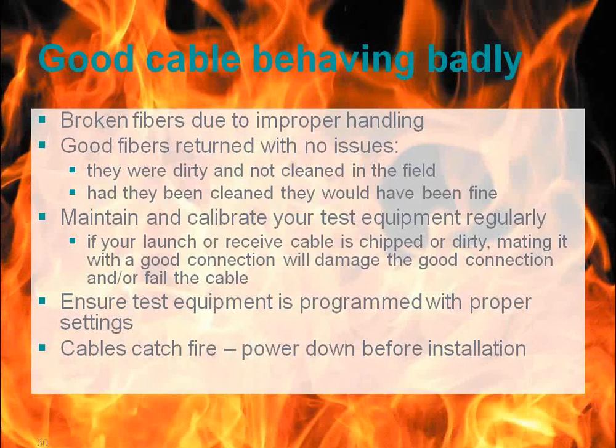Good cables behaving badly. We've been to site, we've seen cables catch fire, and this was because the cable was live. We went to this one site to repair a cable. The climber climbed the tower to drop the top end of the cable down, but did not disconnect it from the equipment at the bottom. So it was still a live cable, it shorted out, and the cable caught fire. Always ensure when handling power cables, any cable, that it is disconnected from the power source.